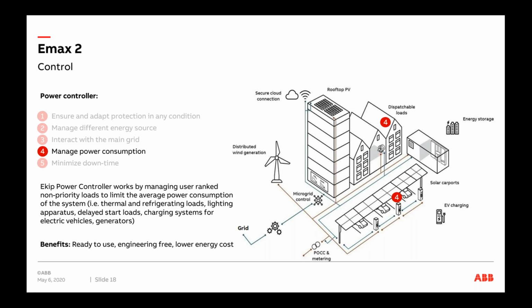Anytime a particular device is probably going through a larger current than required, let's say you'd like to cap the peak use of power from a particular device downstream, Emax 2 can recognize that and then automatically control that breaker through Emax 2 by itself with no external relay, but just the power controller enabled within the breaker. And this can be done up to 15 devices.